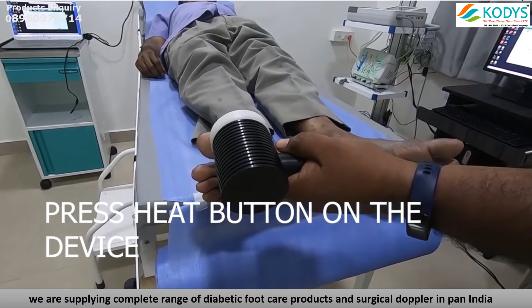After a certain point, the patient will feel the heat perception. Once the patient feels this, you have to press enter. That value will be recorded and it slowly goes back to 32 degrees for the next site assessment. It will give you a beep alerting you to take the test in another extremity, like the first metatarsal. Similarly, in the software we can locate the first metatarsal portion.